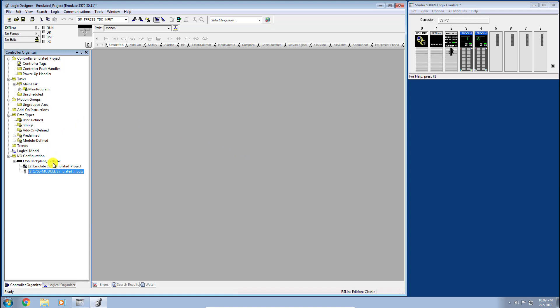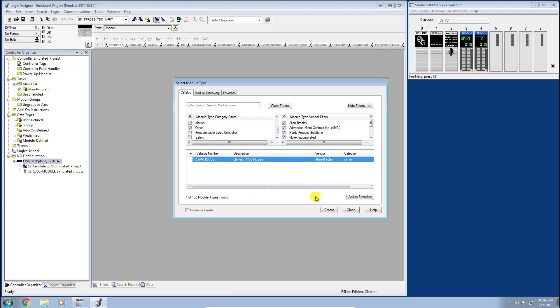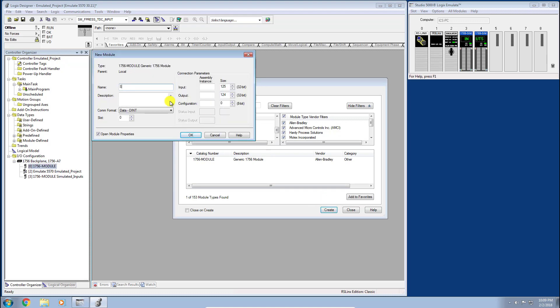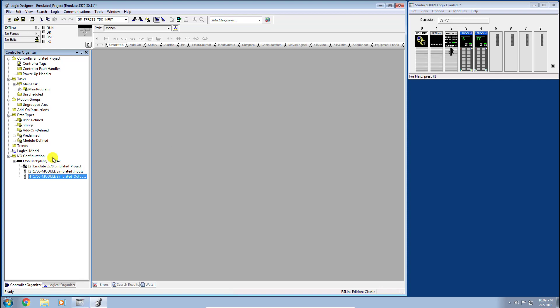A module connection property box opens. Rockwell recommends increasing the Request Packet Interval to avoid connection timeouts on this virtual backplane, so we'll increase it from 5 to 50 milliseconds and click Apply and OK. Now let's add the output module using the same workflow: right-click backplane, New Module, select the Other category simulation module, name it 'Simulated Outputs,' same configuration parameters — assembly instances 1, 2, config 16, size 0 — slot 4, and increase the RPI to 50 milliseconds as well.